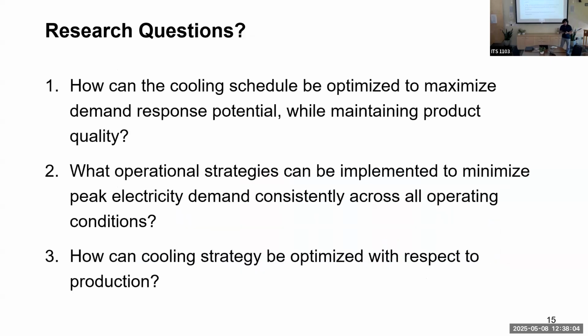So after we established that there is the need for demand flexibility, that cold storage facilities could be a good option for achieving this demand response, and that there's also incentive for the facilities to participate, we put our proposal in with the CEC, and our research questions then were, how can we design the cooling system, or how can we operate the cooling system to optimize that demand response potential? So how can we predict the space temperatures and then operate the system in a way that can maximize that shutdown period? If we can do it for 2 hours, 3 hours, 4 hours, what does that window look like, and how do we calculate and optimize that?